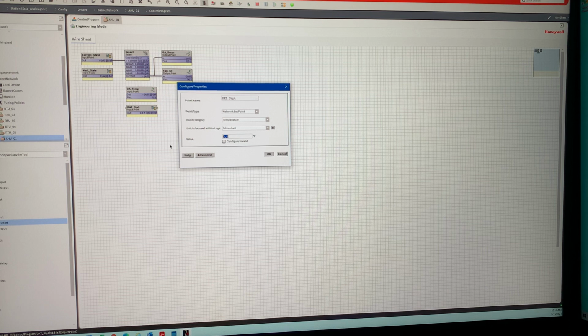Then we're going to do a network set point. We're going to call this DAT_STT. We'll go to here, configure properties. The pop-up screen brings it over here. It's already set up for temperature in Fahrenheit. And let's do 55. Later on, I could show you how we could do a sliding discharge air temp set point based on outside air temperature. Here in Houston, we have a little bit different weather versus just like anywhere else in the country. We have a real large issue with our humidity here, so we have to do a lot of things to take that into account.